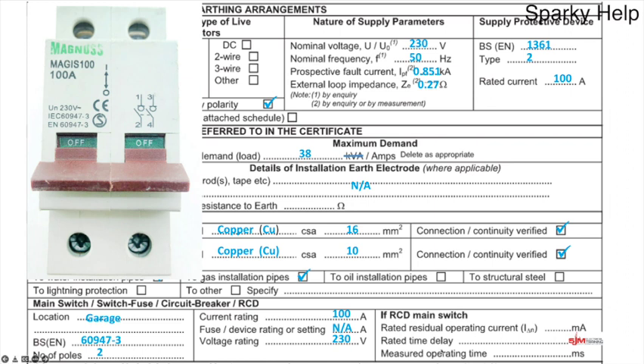The last bit on there is if the RCD main switch. So this is not an RCD, but if it was an RCD, you could put the current rating of it. So that's the I delta n, that's the residual current rating. So that would be 30 milliamp, 100 milliamp, 300 milliamp, 500 milliamp. You get the idea. Next one is suitable time delay, because if you've got one in a TT, you may have other RCDs in line, and therefore you're going to make that one a time delay, and you'd be looking for the manufacturer to quote what the time delay is, because they might say 50% extra of whatever the disconnection time happens to be. And then we've got the measured operating time.